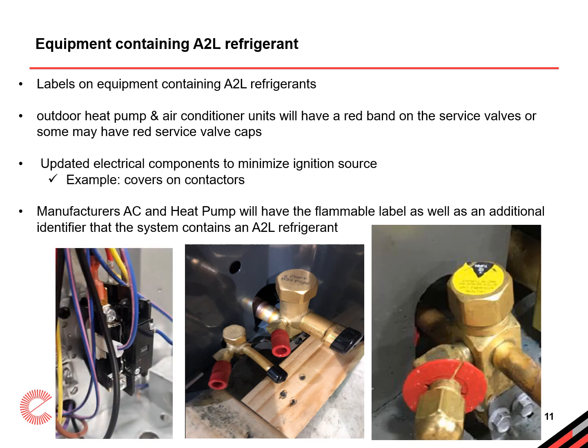Some manufacturers may be implementing updated electrical components designed to minimize ignition risks. One example is the addition of covers on contactors, which could help reduce the exposure to potential ignition sources. While this change has not been fully confirmed, it reflects an industry-wide effort to prioritize safety in light of the mildly flammable nature of A2L refrigerants. We'll keep you updated as more information becomes available regarding this potential implementation. Lastly, equipment containing A2Ls will feature not just flammable labels, but also additional bold visual identifiers that specify the system's refrigerant type. These measures reinforce the importance of clear labeling for safe handling and maintenance.